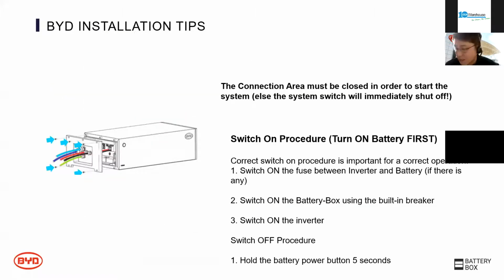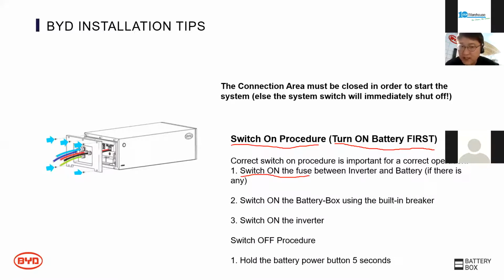Just to cover a bit more on installation tips, because our battery is slightly different from the ones you were doing before, or our old high voltage battery. To switch on the batteries, please remember turning on the battery first, otherwise the battery sometimes will trip the breaker. Basically, turn on any fuses between inverter and battery if there are any, turn on the battery using the built-in breaker, and turn on the inverter last.